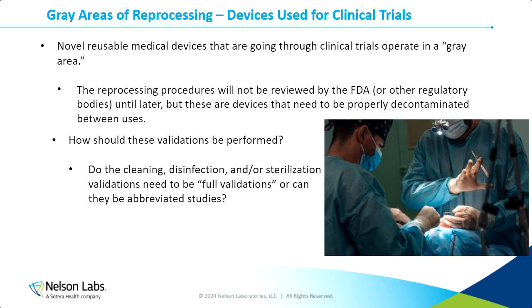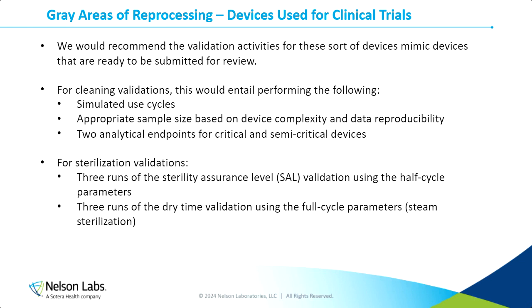We would recommend that the validation activities for devices being used during clinical trials match typical cleaning, sterilization, and disinfection validations, meaning you're going to treat it as if you're submitting the device for review and you're ready to market the device. We would not recommend doing abbreviated studies. We want to make sure that these devices are safe to be reused during these clinical trials, and so the best way to do that is to follow the full recommendations found in the current published standards.